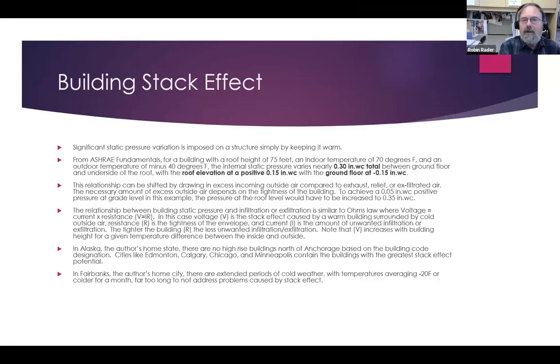This relationship can be shifted by drawing in excess incoming outside air compared to exhaust air or exfiltration. The necessary amount of excess air depends on the tightness of the building. So to achieve 0.05 inches positive pressure at grade, in this example, the pressure at the roof would have to be increased to 0.35.